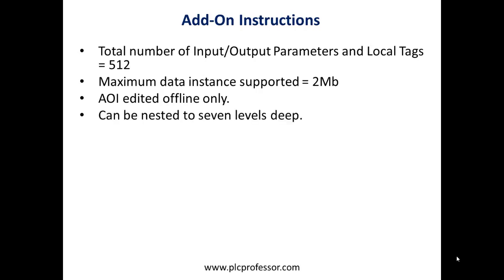You can nest add-on instructions 7 levels deep, just as you could with subroutines. That means you can use an add-on instruction inside of an add-on instruction inside of an add-on instruction, and so forth, up to 7 levels deep. You cannot use a JSR — jump to subroutine — to call an add-on instruction. If we get some time, we may talk about subroutines and passing parameters in and out of subroutines, which is how we used to somewhat accomplish this same task.